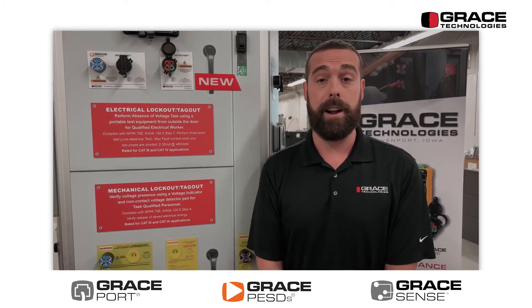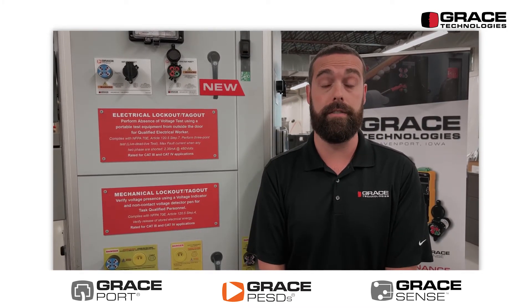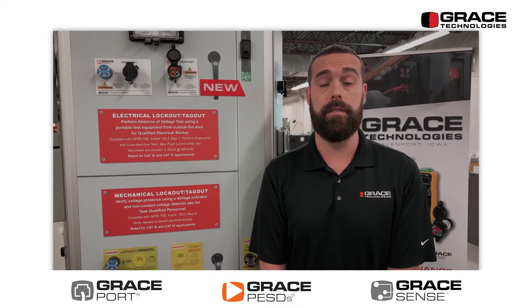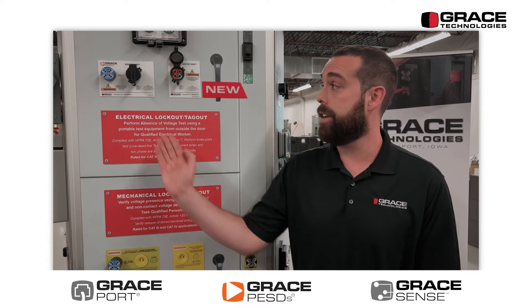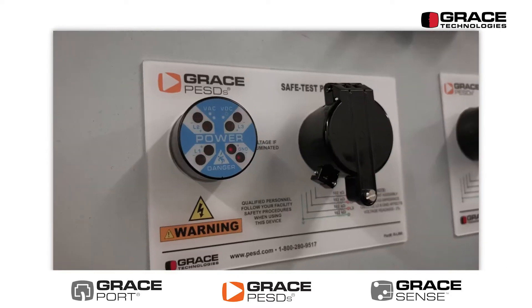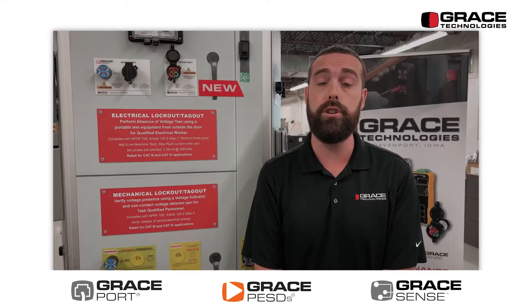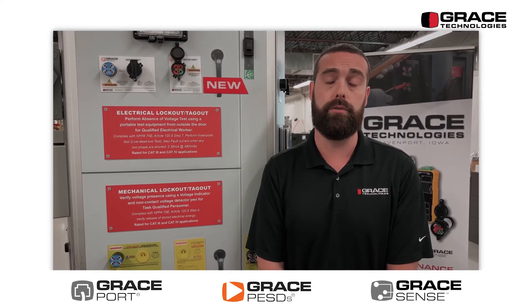Like our previous model, the new 1000 volt rated device can be combined with our existing voltage indicator devices. The voltage indicator is UL listed up to 600 volts AC and 1000 volts DC, and is used primarily for the presence of voltage verification, whereas the safe test point device is used with a volt meter to test for the absence of voltage through closed doors.